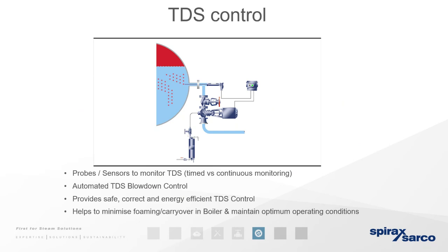And it would just effectively drip through if it's continuous monitoring. So automated, again, it doesn't rely on an operator to have to watch it. You can sample it. So as you can see here, we have the sample cooler. So we can take a sample, we can check. So there's your manual intervention there, but the system itself is looking after itself. And it helps minimize foaming and carryover.